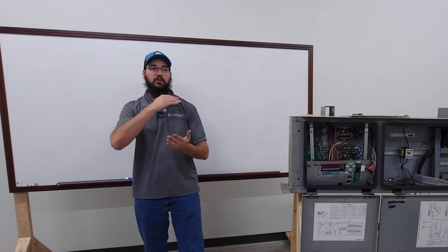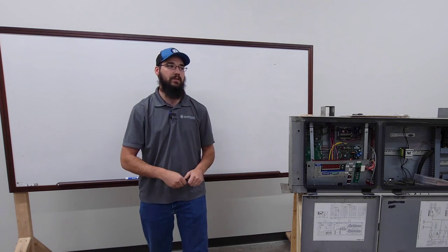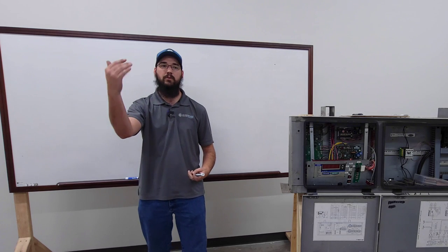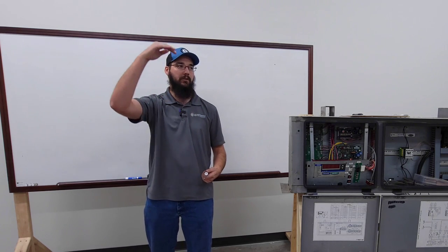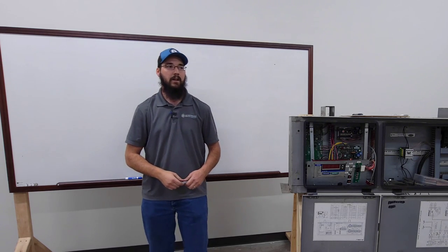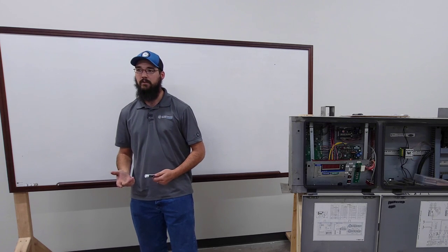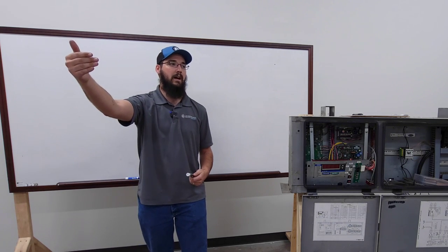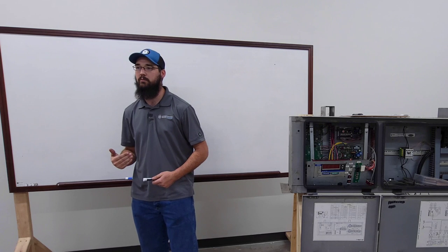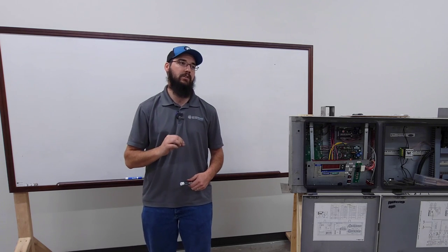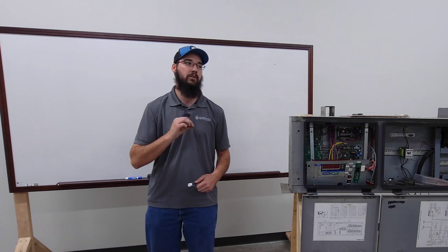We have a different style of troubleshooting now. Before, you used to have a regular ladder diagram and pictorial-type setups, and you'd see everything in series. Your high pressure switch was tied in with your low pressure switch, which ran through those safeties to get to your contactor. That's not the case anymore. And especially the more time goes by, the less we're going to see that. There may be some safeties ran in series, but the vast majority of systems are moving to an IO design.